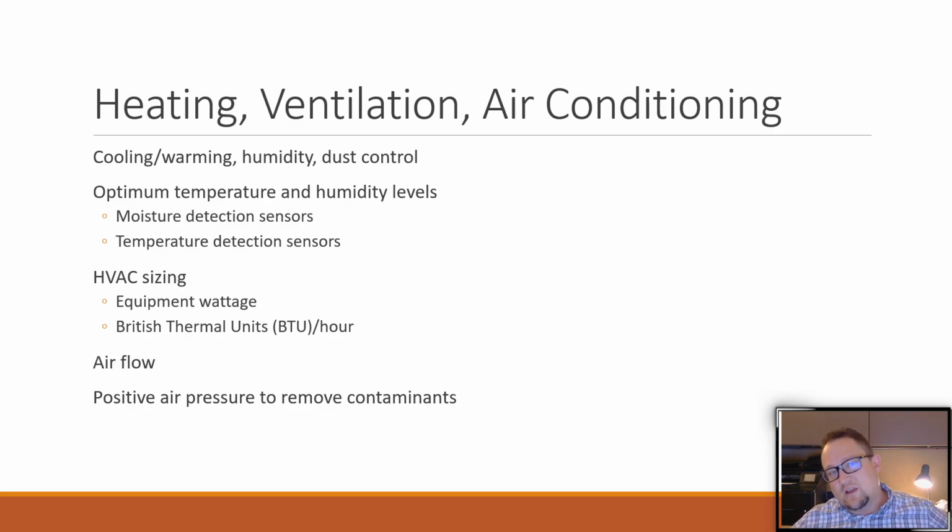What if an attacker gets into your heating and cooling and either turns it off, or turns heating up, or turns air conditioning down, or adds a ton of humidity into your data center? Whatever it may be, we need to make sure that we're monitoring this so that way we know that everything is A-OK and that we have the proper equipment in there. Because the moment that somebody gets in there and starts tampering with us, we need to know if it happens. Because it may just be equipment failure, but it could also be an attack.